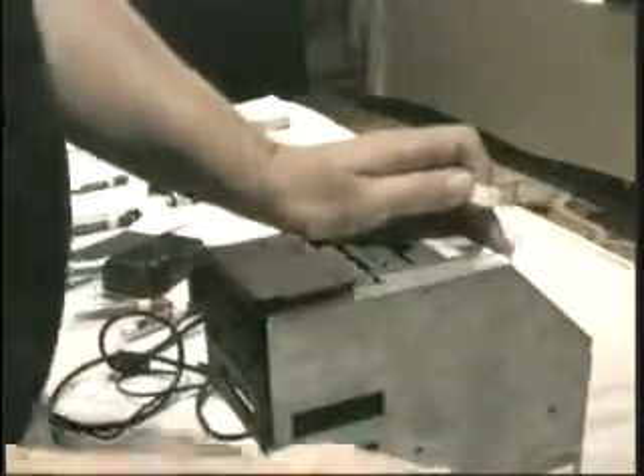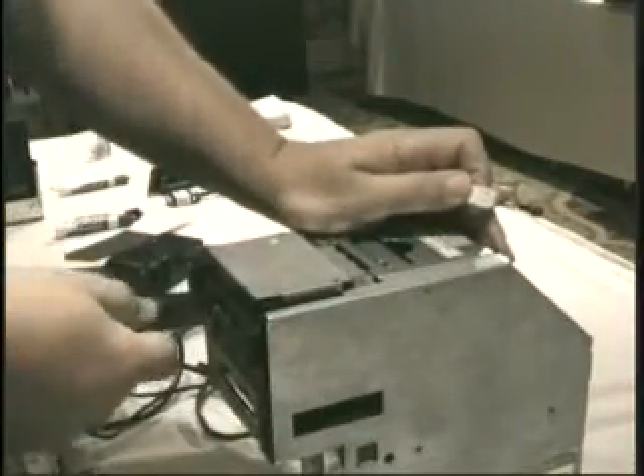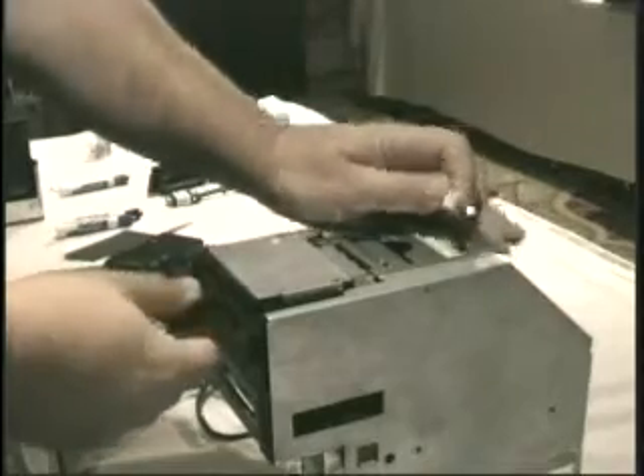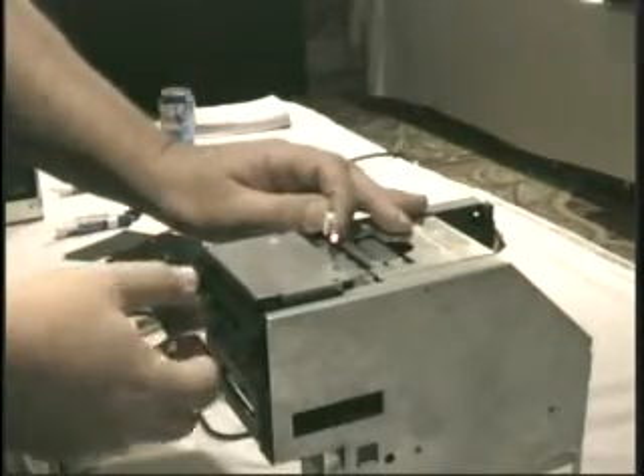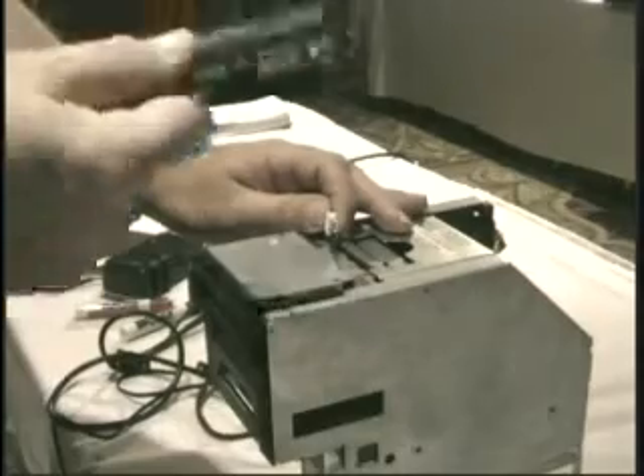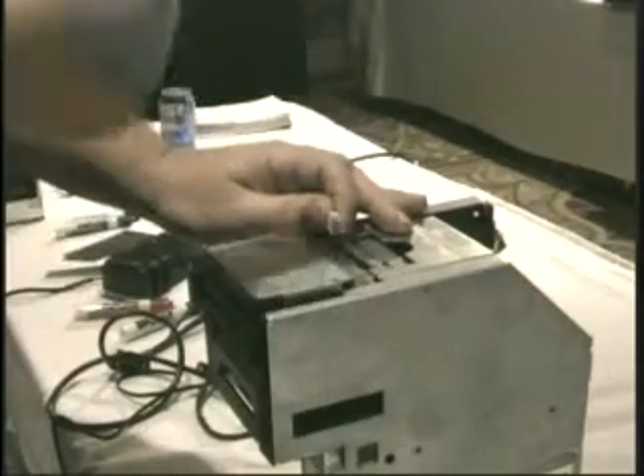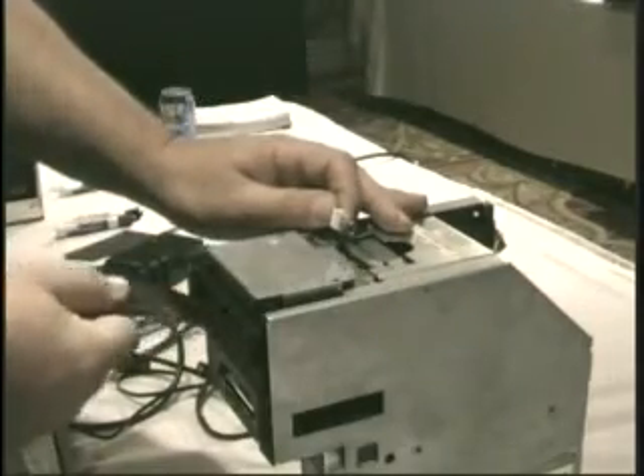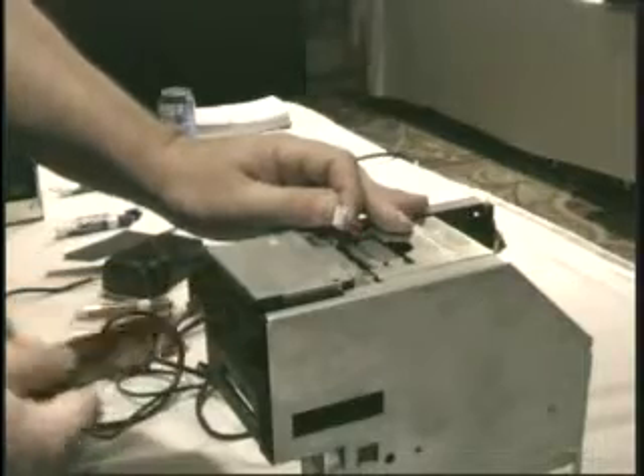Now to slide a card in there, you got to push it a little harder, past those O-rings that are right near the front. For this type of testing I usually use either my ID card or a slot card - it'll slide past those rollers a little easier. You can use a business card, you just got to be careful when you're pushing it in.